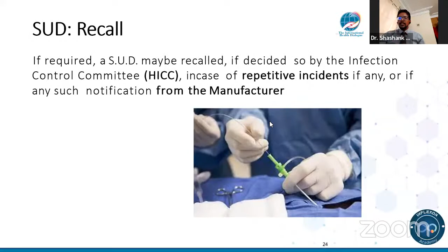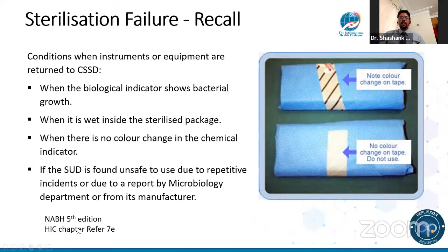So this is one more thing that we need to focus on, in case there's a sterilization failure. This is common. This is not just for SUDs, but in fact for all devices that go through the CSSD, that you plan for a recall. In case there's a biological indicator failure, then the entire lot till the last biological indicator was negative has to be recalled. If it is just a class 1 or a class 4 or a class 5 failure, only that pack gets recalled. In case it is a Bowie-Dick failure, then nothing else gets processed during this time. So in case you want to know more, this is an important requirement from the NABH point of view. It's there in the 5th edition. Reference is given below. Yeah, next slide, please.